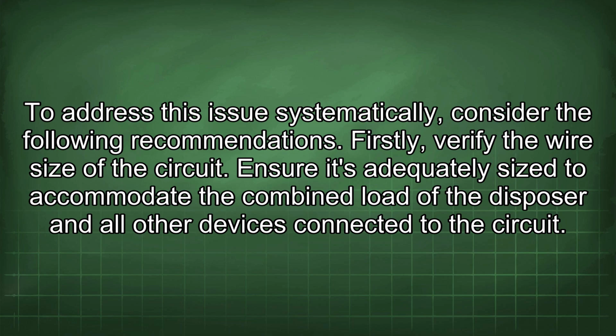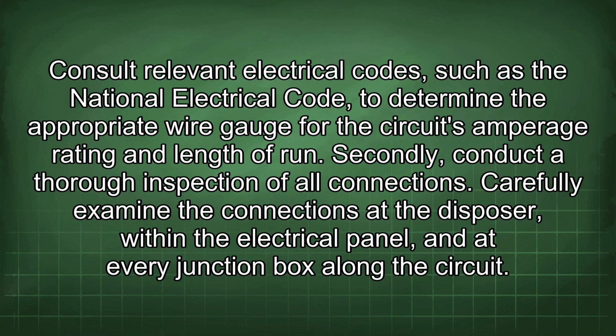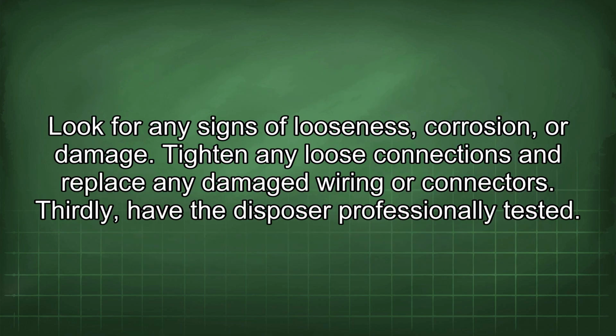Firstly, verify the wire size of the circuit. Ensure it's adequately sized to accommodate the combined load of the disposer and all other devices connected to the circuit. Consult relevant electrical codes, such as the National Electrical Code, to determine the appropriate wire gauge for the circuit's amperage rating and length of run. Secondly, conduct a thorough inspection of all connections. Carefully examine the connections at the disposer, within the electrical panel, and at every junction box along the circuit. Look for any signs of looseness, corrosion, or damage. Tighten any loose connections and replace any damaged wiring or connectors.